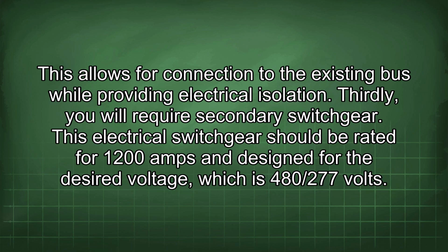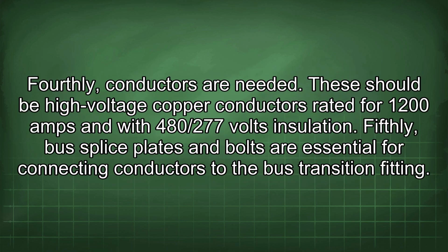Thirdly, you will require secondary switchgear. This electrical switchgear should be rated for 1200 amps and designed for the desired voltage, which is 480/277 volts. Fourthly, conductors are needed. These should be high-voltage copper conductors rated for 1200 amps and with 480/277 volts insulation. Fifthly, bus splice plates and bolts are essential for connecting conductors to the bus transition fitting.